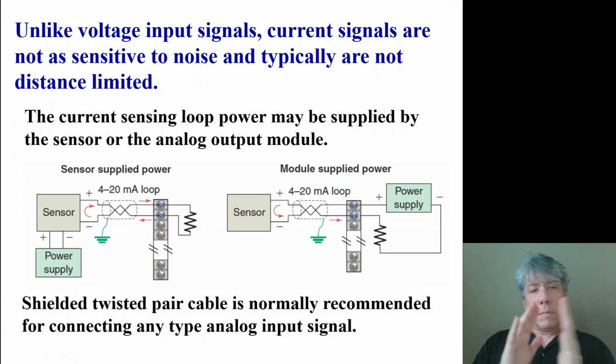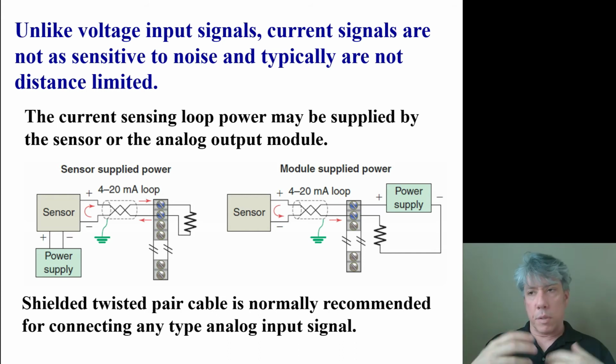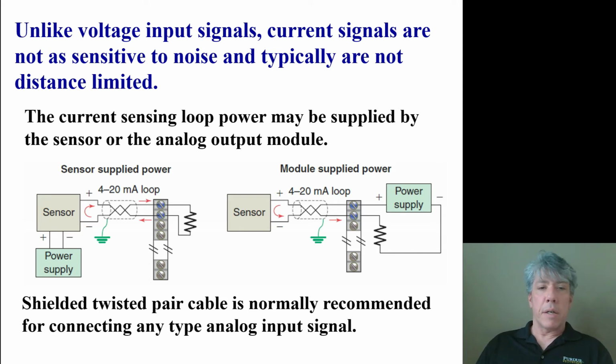Now, which one would we want to select? Let's go back to the idea that there are current sensors and then there are voltage signals. Basically these two signals are an option. We can choose either one very commonly. Voltage signals are what most people think of when they're just learning and they want to use it, but honestly a current signal is typically the better option.